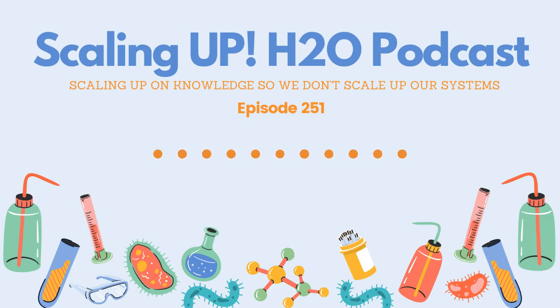Maybe the probe was not out of calibration. Never a bad idea to clean a probe every time you come across one. So you didn't do anything you shouldn't have done already. You're just starting the diagnosis process. Well, now let's go to how the controller is controlling the concentration, and that's with a valve. A valve that is letting high concentrated system water out, so makeup can now come in and dilute the rest of the water in the system.